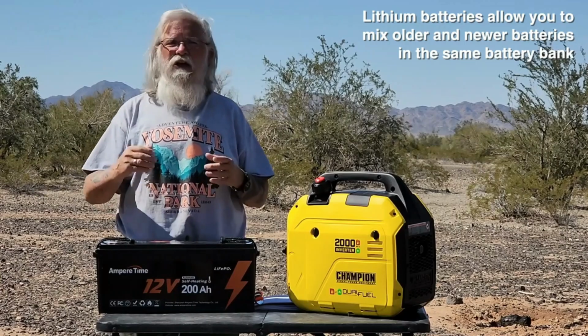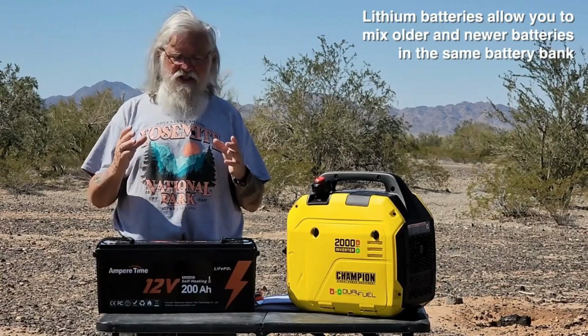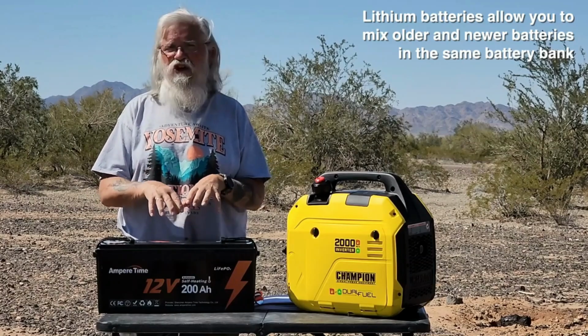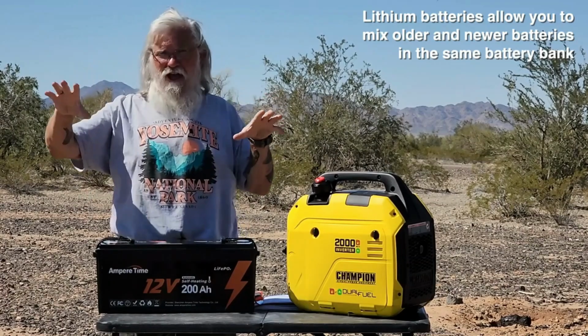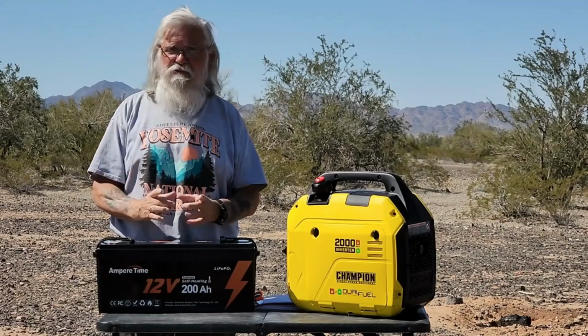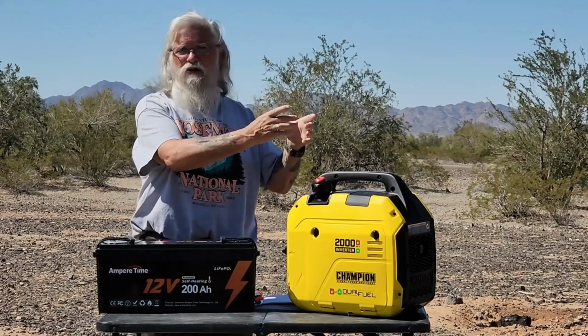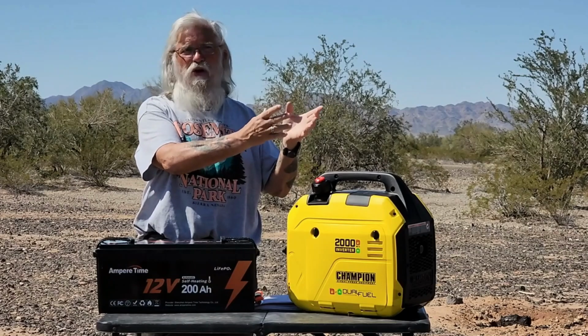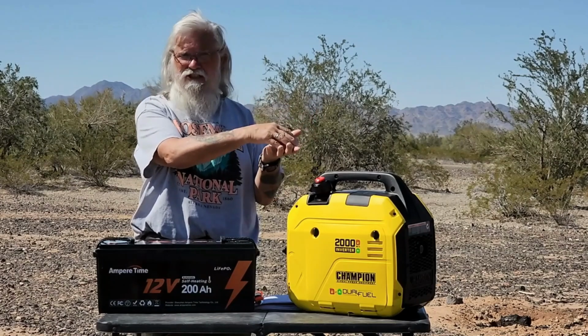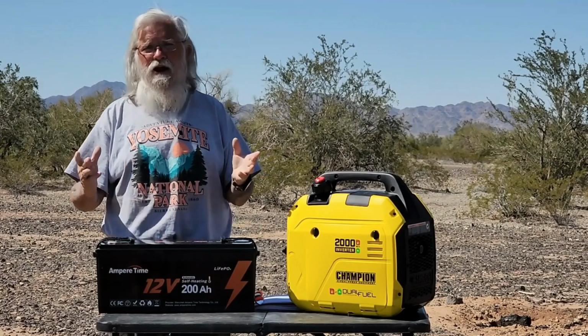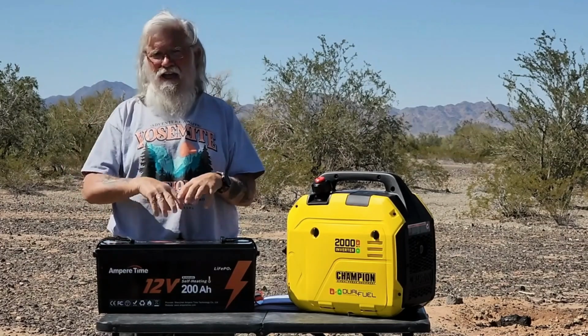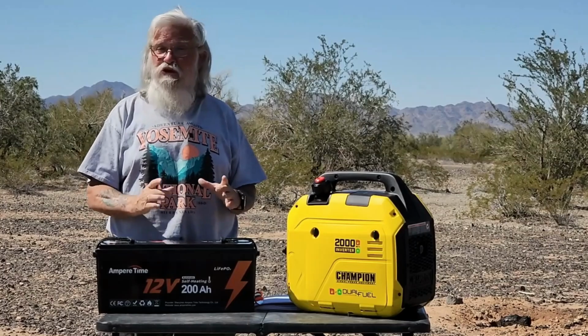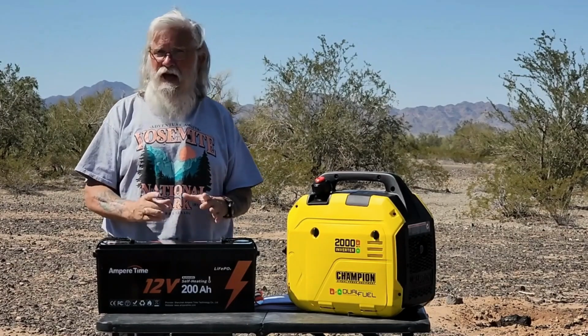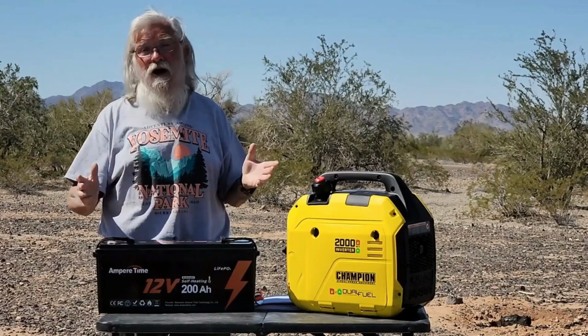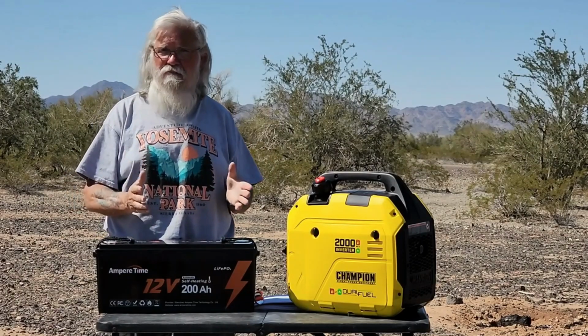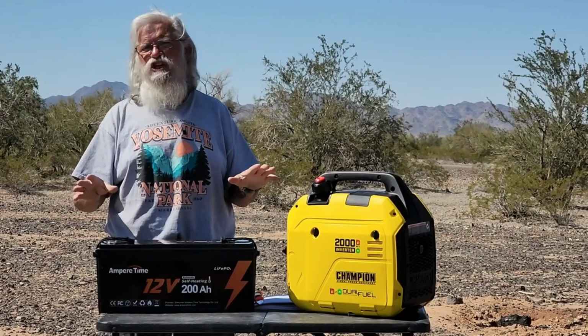The BMS reads the power coming in and sorts it for the particular battery. It doesn't look at the entire system, it looks at this battery. So while an older battery has a BMS that says 'I'm older, I can't take as much,' it'll put in less, and this battery will say 'I'm brand new, I can take a lot, put it all in.' You get that individual control with an individual BMS, meaning you're not tied to buying all your batteries at the same time, in the same condition. To my mind, that's a huge advantage.